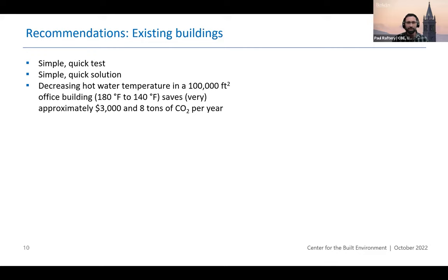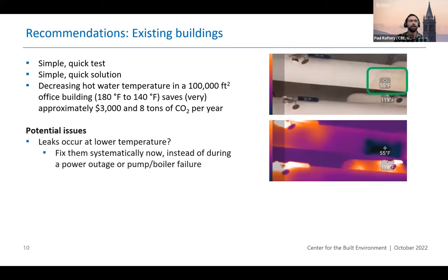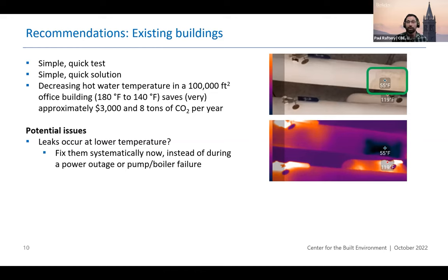Based on the data we have, in a 100,000 square foot building, dropping the supply water temperature by 40 degrees for a substantial portion of the year will save about $3,000 or 8 tons of CO2. That's obviously very approximate. The potential issues you can run into are that some of these systems do leak when you lower the supply water temperature, especially in older buildings 20, 30, 40, 50 years old. For that reason, many of these systems are operated 24-7 to avoid those leaks.